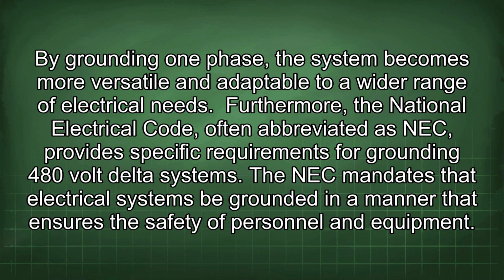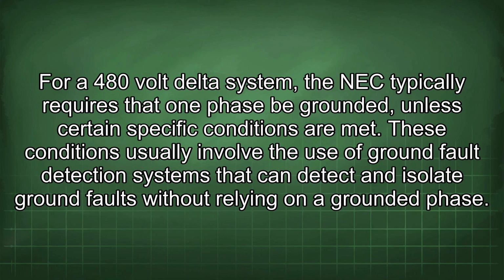Furthermore, the National Electrical Code, often abbreviated as NEC, provides specific requirements for grounding 480-volt delta systems. The NEC mandates that electrical systems be grounded in a manner that ensures the safety of personnel and equipment. For a 480-volt delta system, the NEC typically requires that one phase be grounded unless certain specific conditions are met.